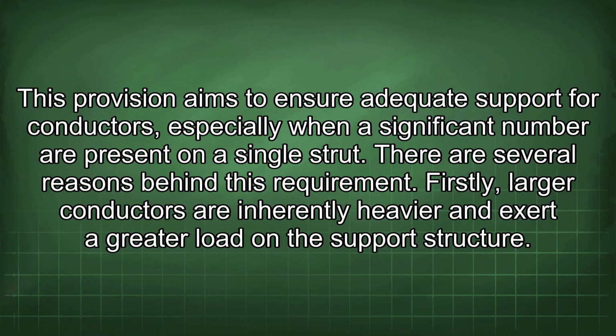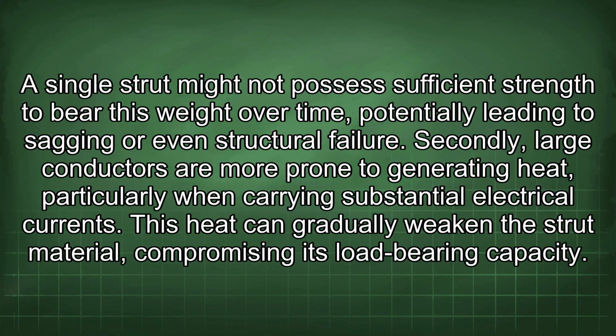There are several reasons behind this requirement. Firstly, larger conductors are inherently heavier and exert a greater load on the support structure. A single strut might not possess sufficient strength to bear this weight over time, potentially leading to sagging or even structural failure. Secondly, large conductors are more prone to generating heat, particularly when carrying substantial electrical currents. This heat can gradually weaken the strut material, compromising its load-bearing capacity.